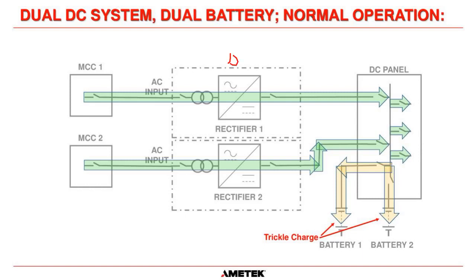Let's say you set this charger at 135 volts and you set this charger at 135 volts. Let's say this cable is 10 meters. I'm European, sorry. And this cable is 20 meters. This cable here is going to have more of a cable drop, so that is going to affect the voltage. So really at the DC panel, you might see that this one here is going to have 134 volts and this one here is going to have 135 volts. And therefore, this one here is going to supply more of the load because it has a higher voltage. The charger with the highest voltage will supply the majority of the load. And that's not a bad thing. That's just the design of the system.